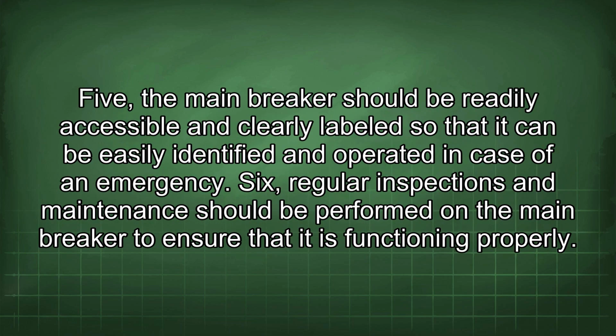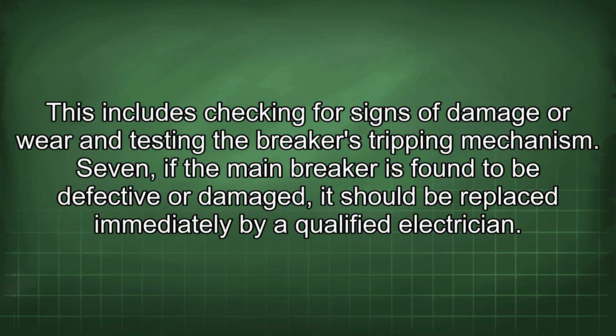5. The main breaker should be readily accessible and clearly labeled so that it can be easily identified and operated in case of an emergency. 6. Regular inspections and maintenance should be performed on the main breaker to ensure that it is functioning properly. This includes checking for signs of damage or wear and testing the breaker's tripping mechanism.